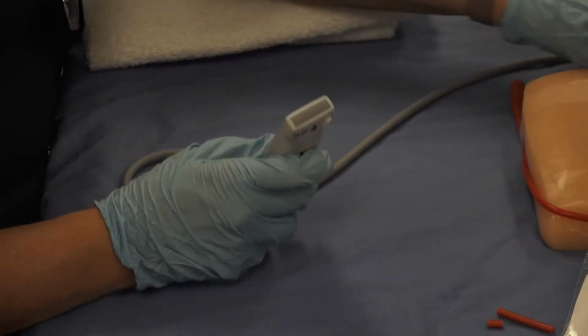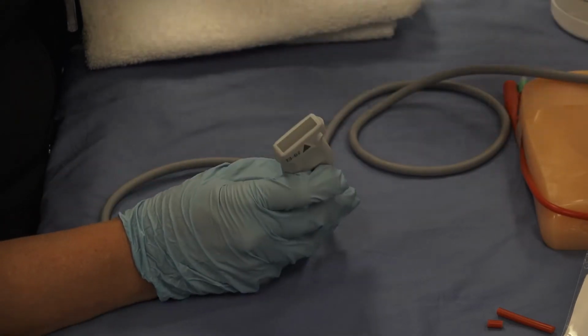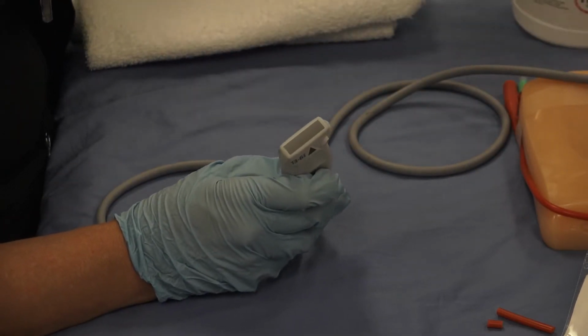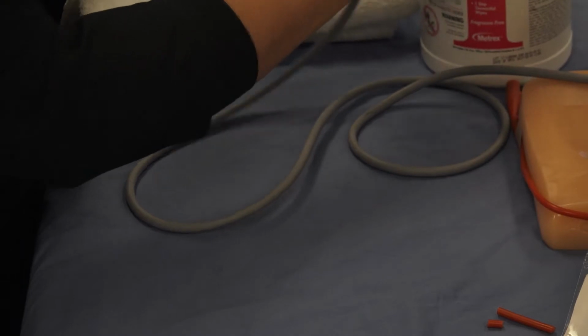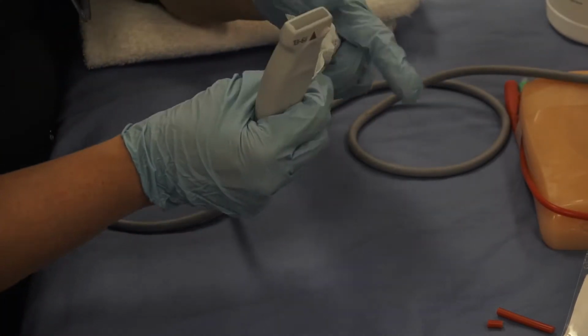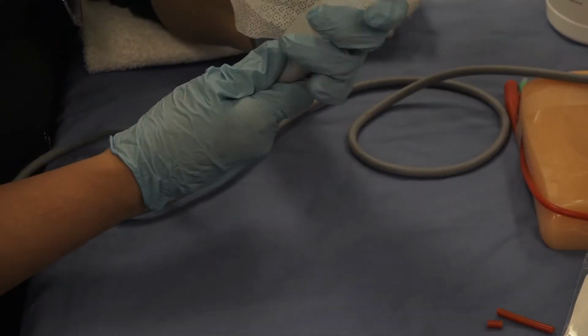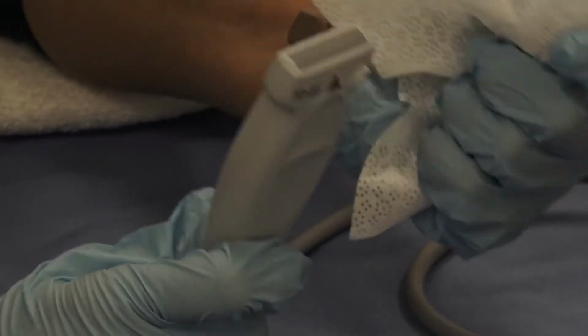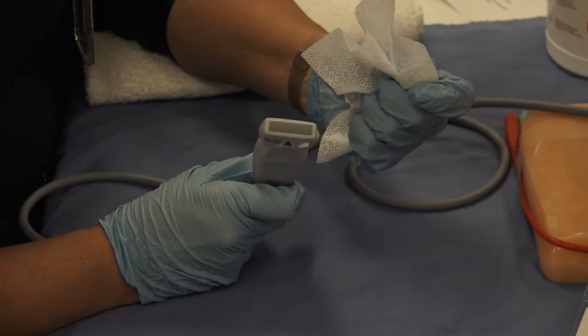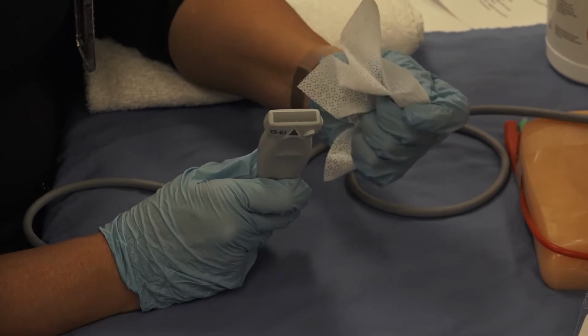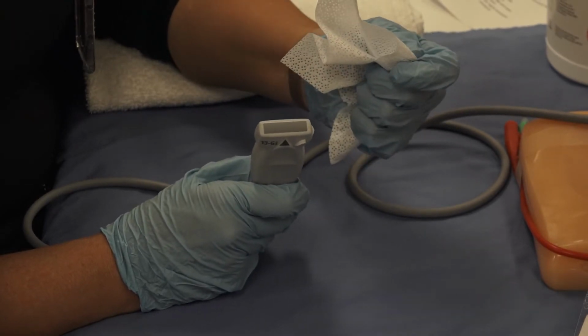Now, an important part of using a probe is to remember to clean it regularly, and what this means is before and after each use. When you clean it, use manufacturer-approved wipes. Because if you use the wrong wipes, you can actually damage the probe and it will void the warranty.